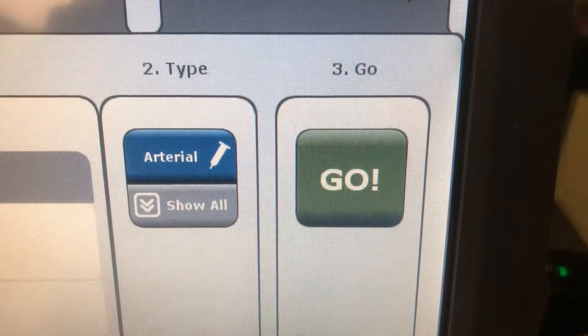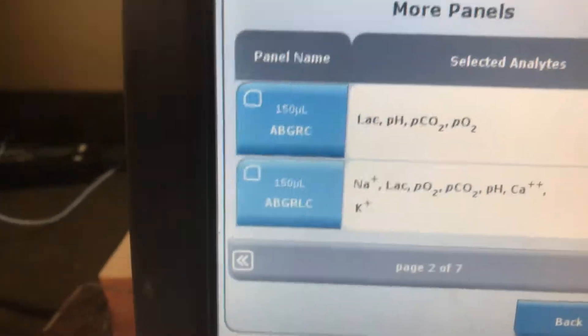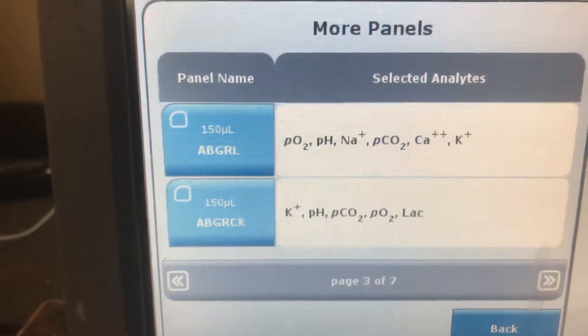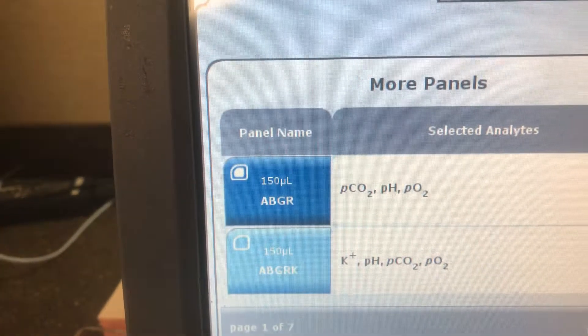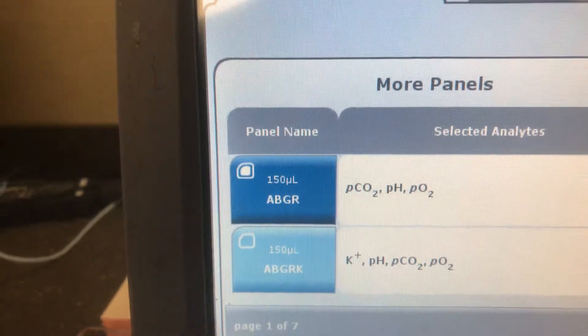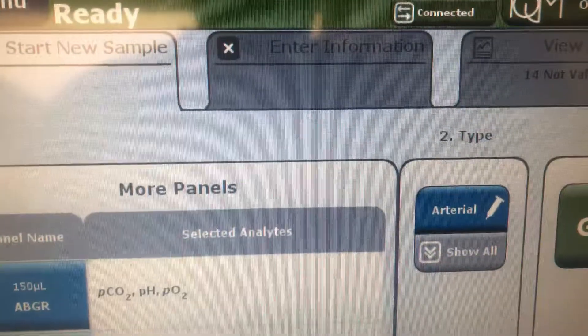Alright, going to show you how to do an ABG here at the hospital. First thing on the GEM4000 you have to pick your panel, then you have to pick your sample, then you have to pick your go button. If you don't see what you want here, push this button — it moves you through different pages of available samples. Today we're just going to do an arterial blood gas, so once we have that picked and we know it's arterial...